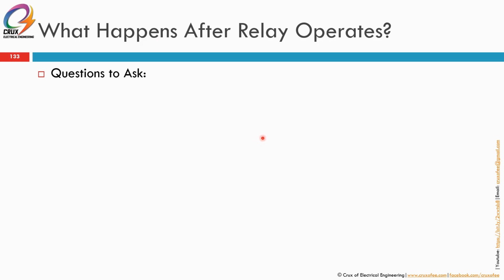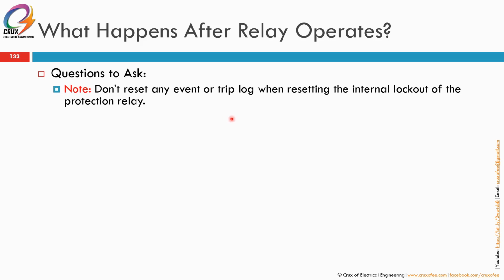So the easiest way is if you go there and reset and restart. So that's a big no. Never do that. So, do not reset any event or trip log when resetting the internal lockout of the protection relay. Obviously, these are the kind of things that the chargeman or the engineer would normally do. You would like to revive your power system, so obviously you have to reset some lockout relay, some internal lockout, before you are able to energize the breaker back. But make sure when resetting those relays, do not wrongly reset any event or trip log.